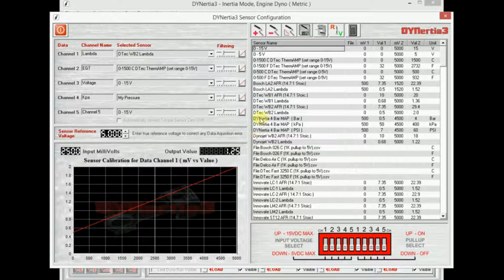If we had a non-linear sensor, let's say channel 5 here - non-linear being something like a coolant temperature sensor, which is a variable resistance. Here's a common Bosch one. I'll choose a degree C calibration. So you can see it has a curve applied to it.